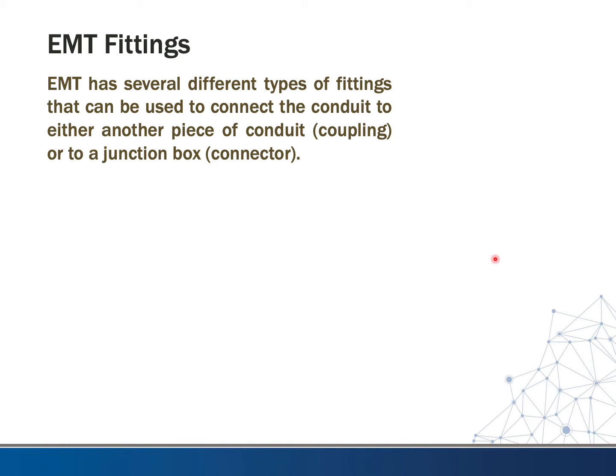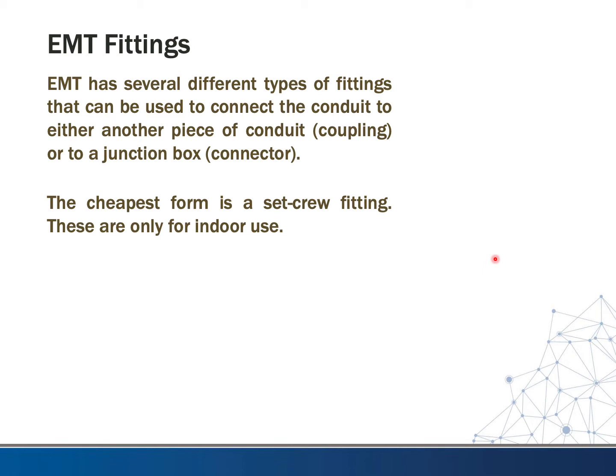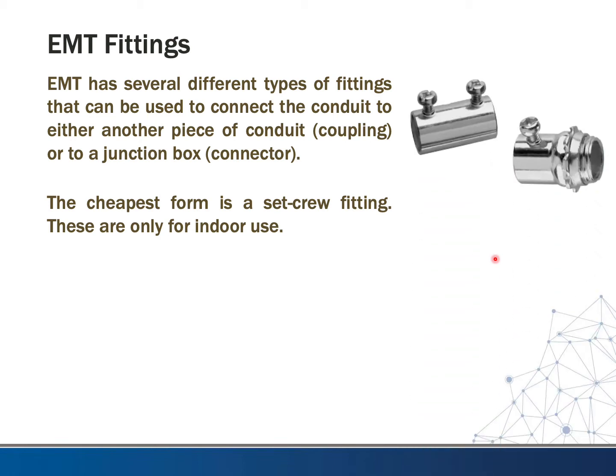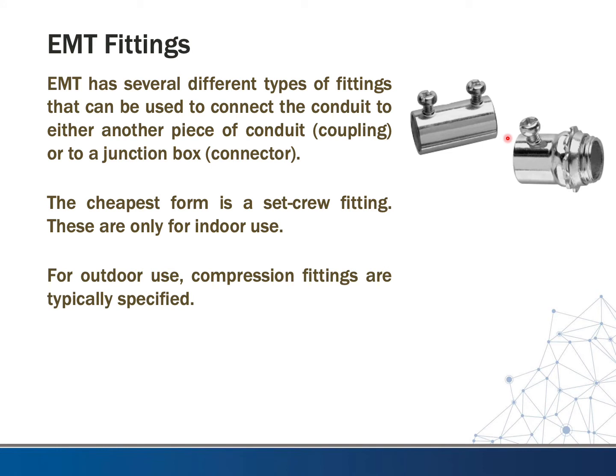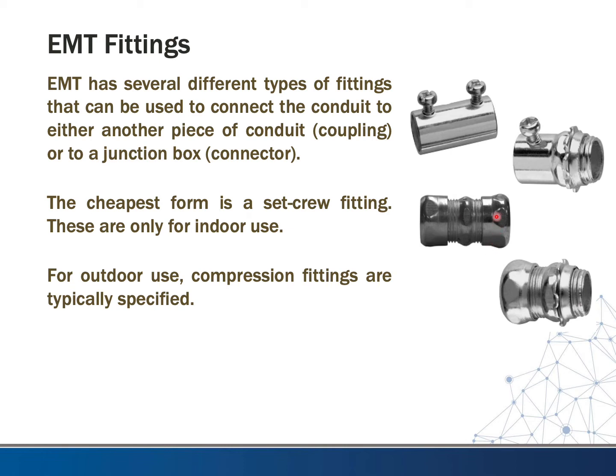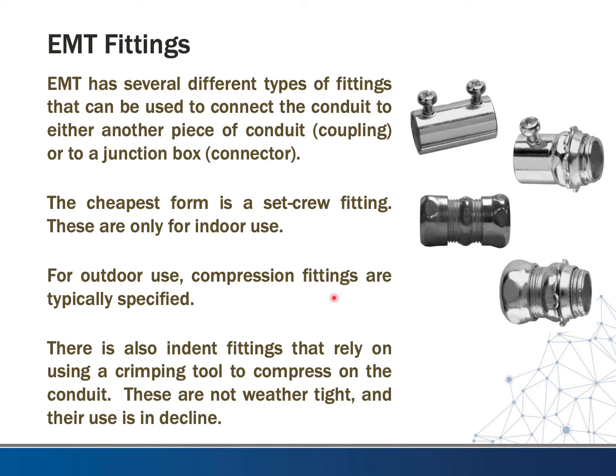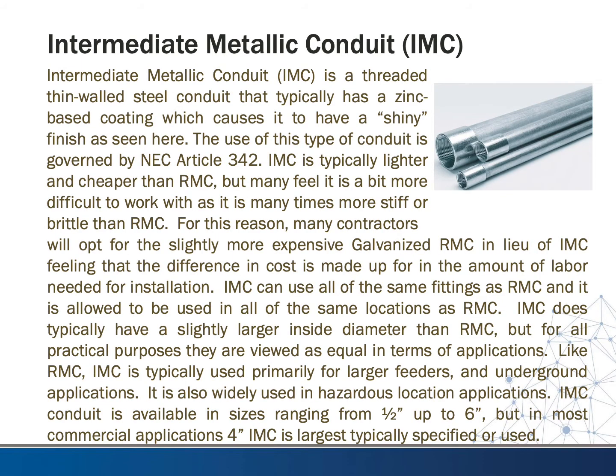EMT has several types of fittings used to connect conduit to another piece of conduit — called a coupling — or to a junction box — called a connector. The cheapest form is a set screw fitting, for indoor use only, identifiable by a prominent set screw. For outdoor use, compression fittings are typically specified; the tapered threaded portions compress tighter as you screw down, creating a liquid-tight connection. There is also an indent fitting that uses a crimp tool to compress onto the conduit with two indents to hold it in place. Indent fittings are not weather-tight and their use is in decline because the connection is not always reliable.